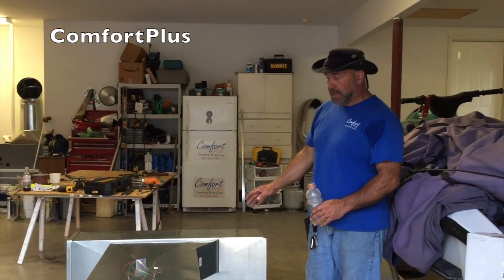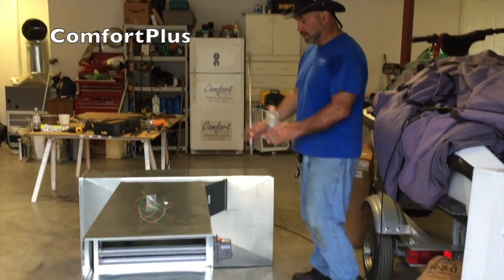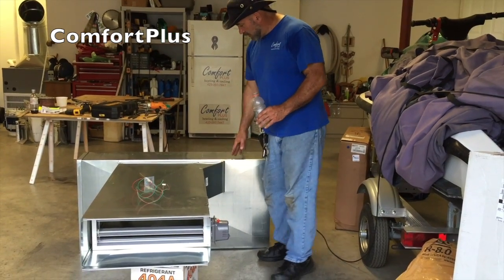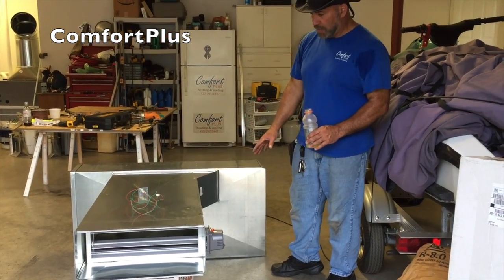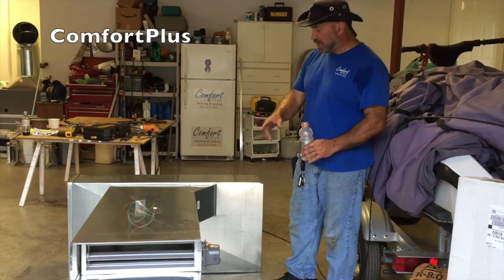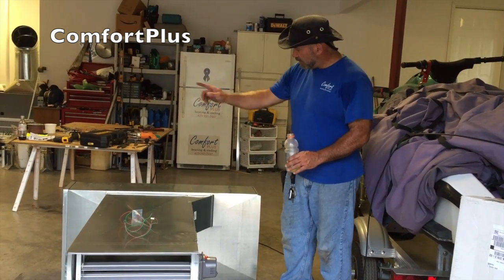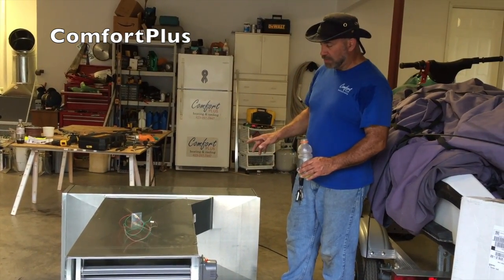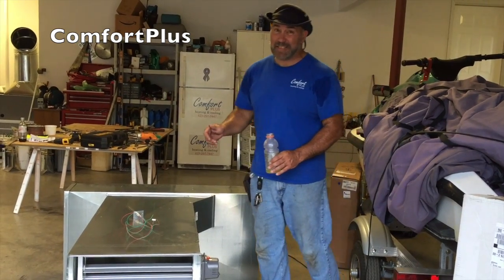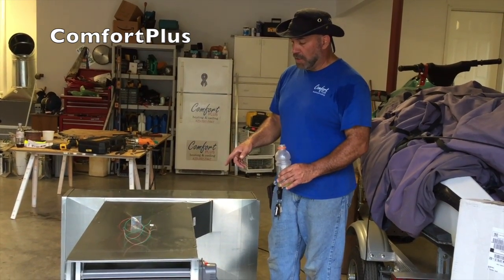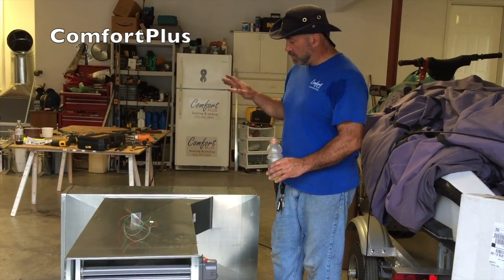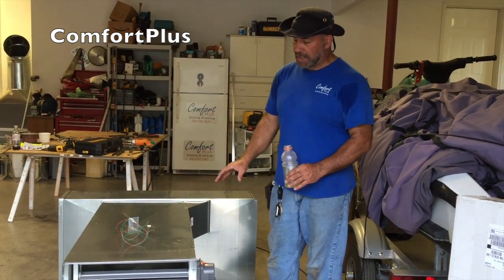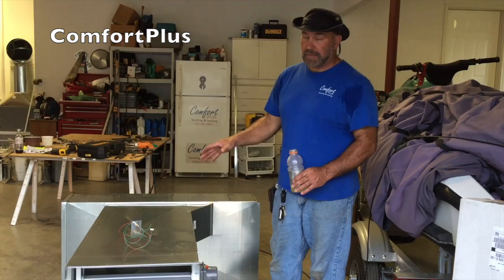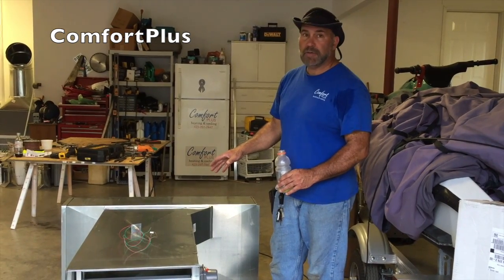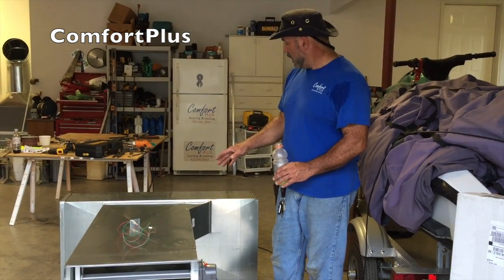Okay, this is the trunk duct with the two supplies coming off of it now, kind of mocked up here on the floor. Thing's about 9 foot in this dimension, 4 foot in this dimension, and about 24 inches tall, so I can actually get this under the crawl space from here. So what I may go ahead and do is screw everything, mastic everything, insulate everything, and it'll be so much less to do when we get underneath the house.